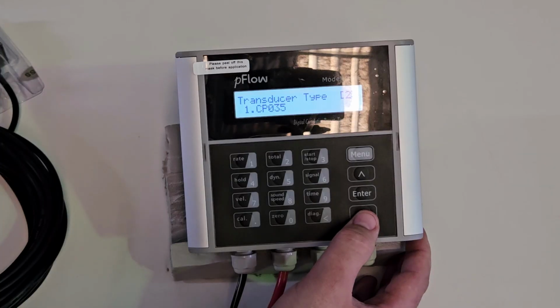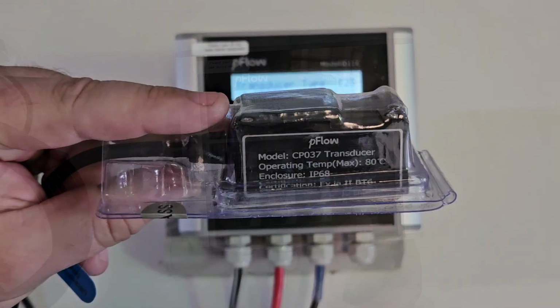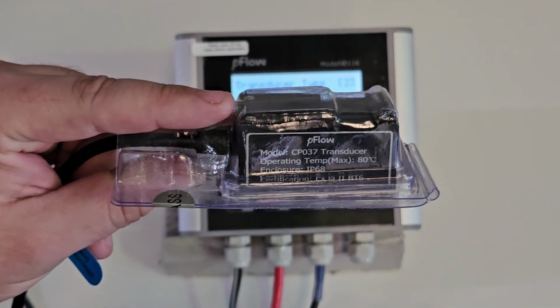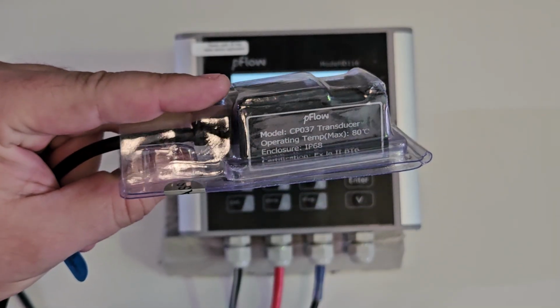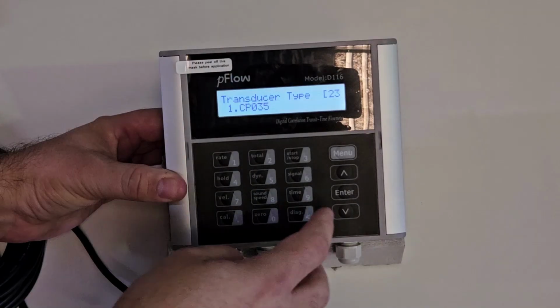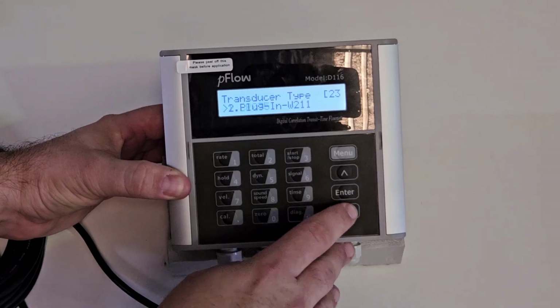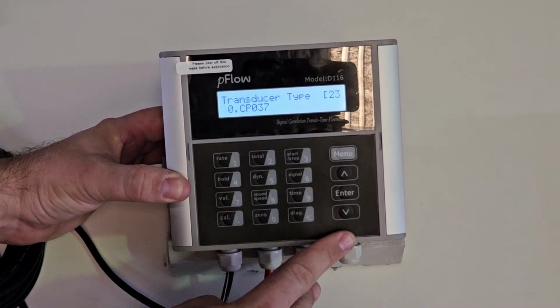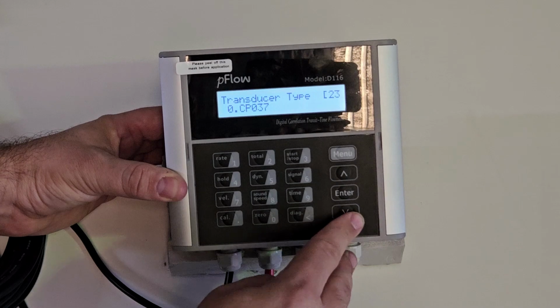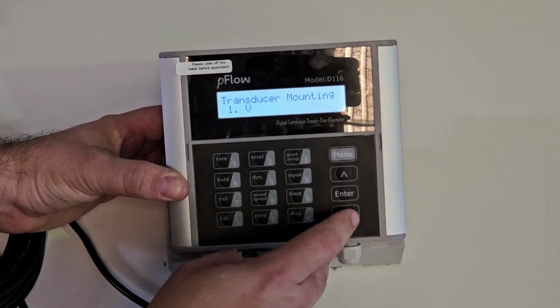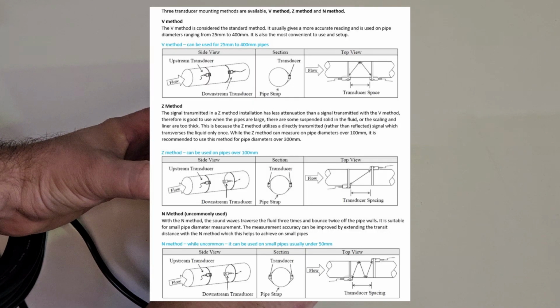Now press down again. The next option is for transducer type. Please check the label on your transducers or confirm the model you purchased. In this case, we can see it should be CP037 as marked on the sensors. Press enter, scroll the list of options, and choose your type accordingly. Press down again for the next menu. This is the option for transducer mounting method. We are using the most common and easy to use V method, but other methods are available and can be selected here.